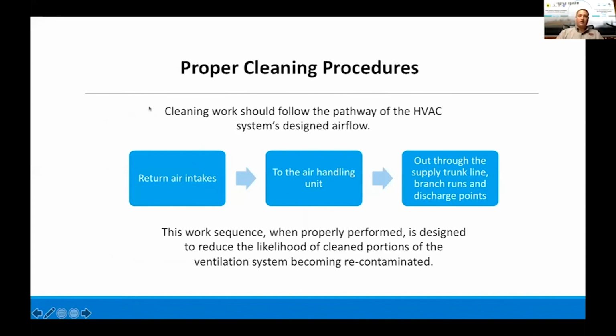Proper cleaning procedures. Cleaning work should follow the pathway of the HVAC system's design. So I noticed in the previous session that there were arrows that showed the air coming in and the air going out. Here, our cleaning process starts with cleaning the return intakes first, so any area where the air gets sucked in, then cleaning the air handling unit and its components, and then lastly working downstream of the air to clean the supply trunk line and all the branches that come out. Because it doesn't make any sense to do these things oppositely, especially if you have to turn the system back on the same day. This work sequence, when properly performed, is designed to reduce the likelihood of clean portions of the ventilation system becoming recontaminated.